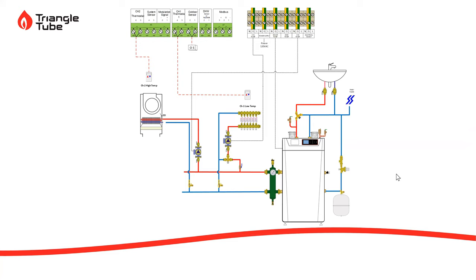Josh, a question came up with regards to the boilers themselves. The low water cutoff that's installed inside these, is it the pressure type low water cutoff where it activates on low pressure? Yeah, it's a pressure switch low water cutoff. It's approved as a low water cutoff.